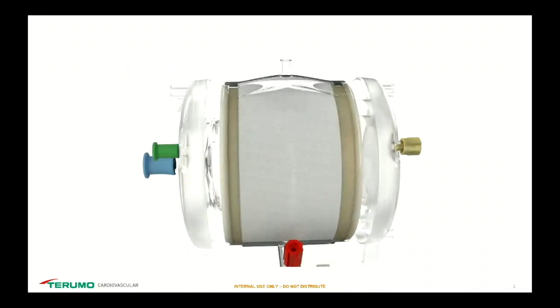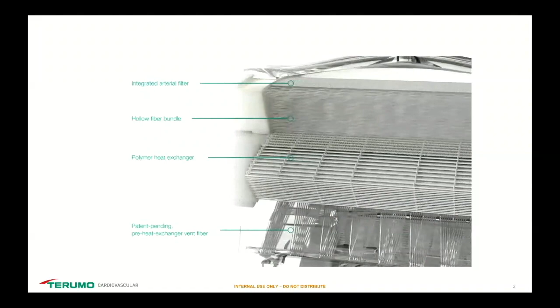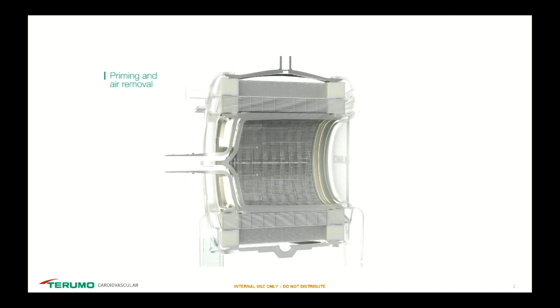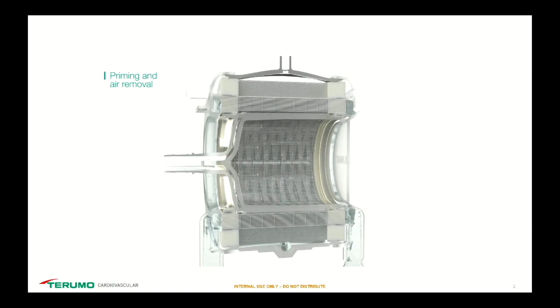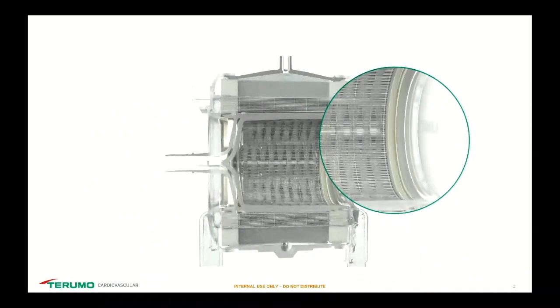Let's take a closer look inside the CAPIOX NX19 oxygenator. Priming and de-airing the CAPIOX NX19 oxygenator is fast. First, water fills the heat exchanger through the bidirectional water ports and flows on the inside of the polymer capillaries. Next, prime solution enters the oxygenator. As fluid fills the heat exchanger and fiber bundle, air rises to the top of the device and exits through the Prime Assist port. CAPIOX NX19 oxygenator features a new patent-pending air removal technology. This hollow fiber technology-placed pre-heat exchanger removes air and prevents it from becoming trapped inside the heat exchanger.